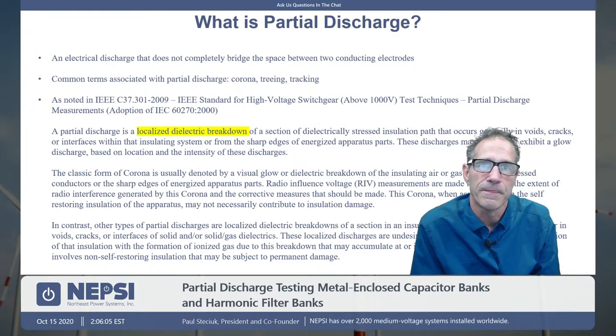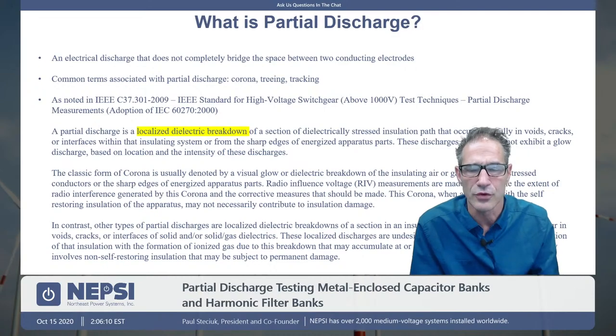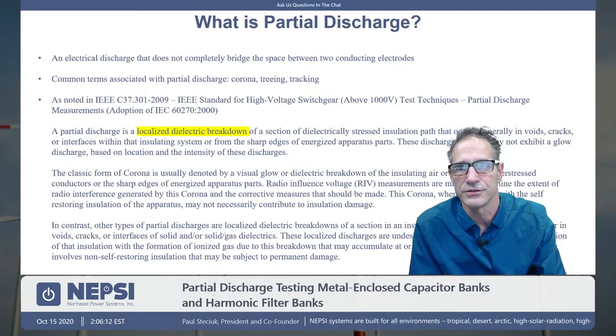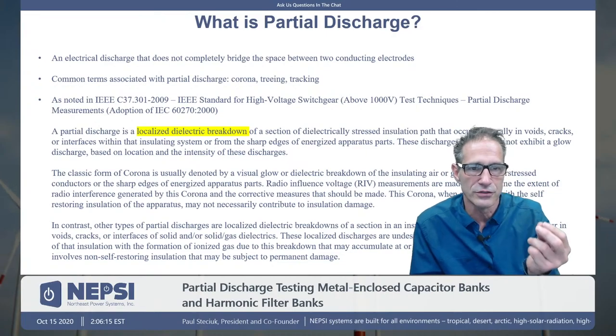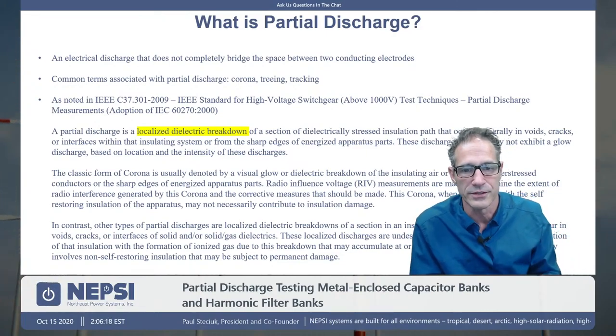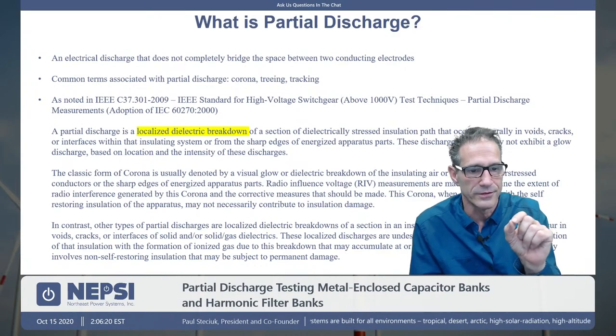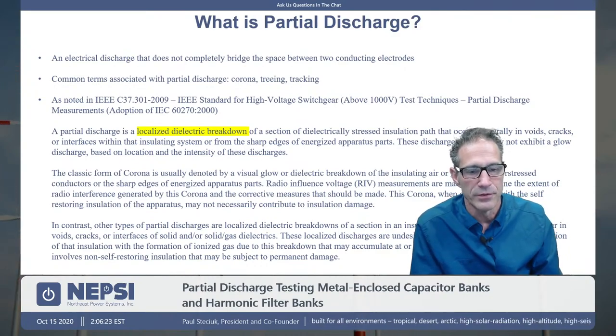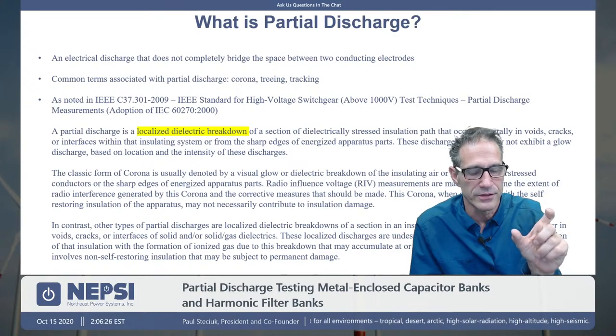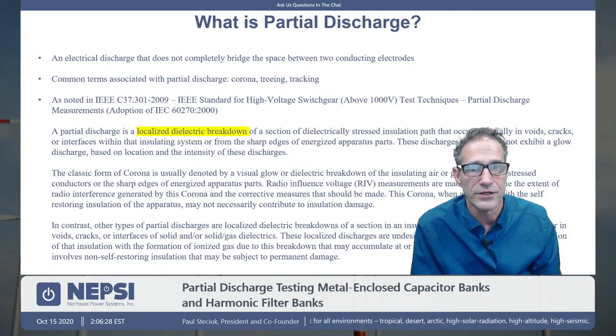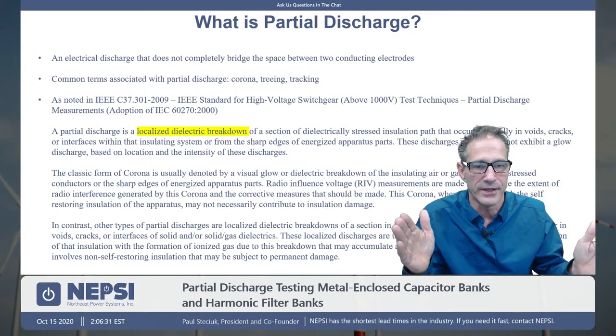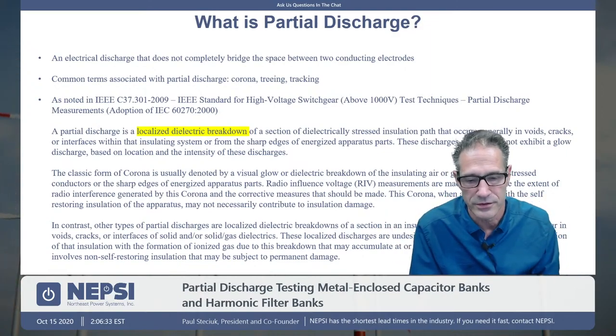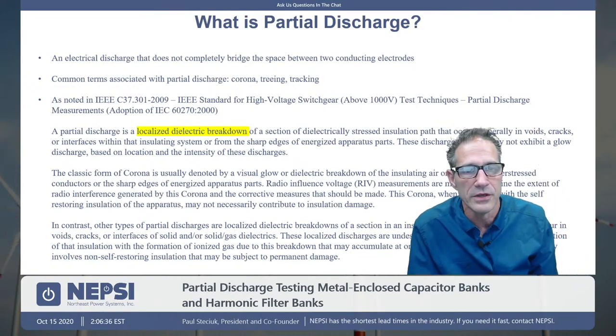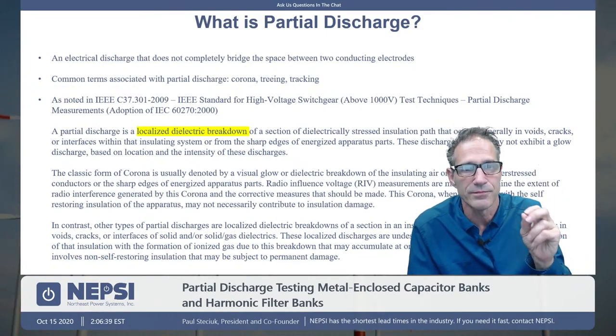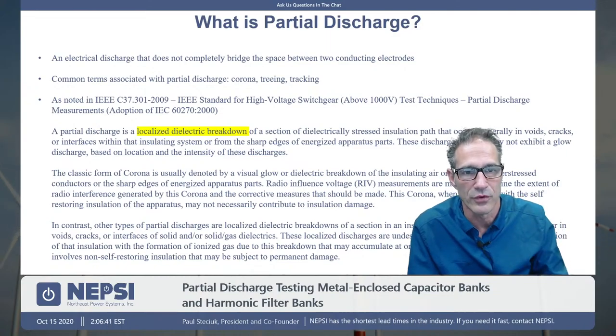So we're talking about partial discharge, and what is partial discharge? The first thing is partial discharge is a discharge within the insulation or on the surface of insulation. It's like a micro short circuit you can almost think about, but it's a discharge within a short distance within insulation or along the surface that doesn't actually bridge the gap. A lot of times you hear this when you're underneath a power line, you hear a little snapping and cracking and popping, and that's partial discharge, and sometimes we might call that corona.